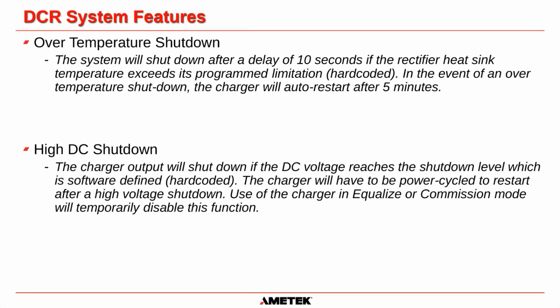We have an over temperature shutdown feature that will happen after 10 seconds of the rectifier heatsink exceeding a pre-programmed limitation. If this over temperature shutdown happens, the DCR will be given 5 minutes to cool down, and then it'll restart by itself. We have a high DC shutdown, so the high DC voltage shutdown. It'll shut down if the DC voltage reaches a level which is software defined. The charger will need to be power cycled to restart after a high voltage shutdown, or needs to be power cycled manually.